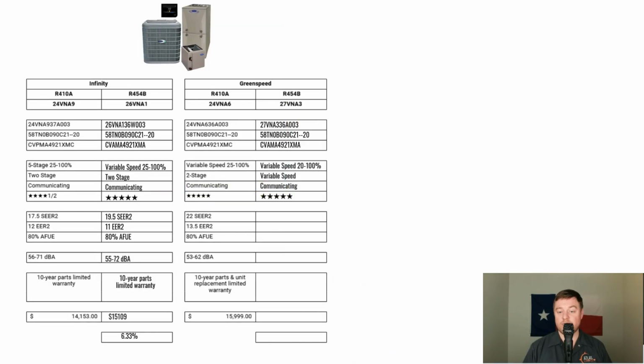Now both of these systems are fully communicating, making them a system that learns its environment and can optimize the indoor climate and efficiency specifically for you. And I'm not going to go into all the details because we touched on that earlier. And for efficiency, the old 410A system was able to deliver 22 SEER in efficiency, and the new R454B system delivers the same 22 SEER. Now for EER2, the 24 VNA6 was able to accomplish 13.5, and the 27 VNA3 did drop some to 12.5 EER2.